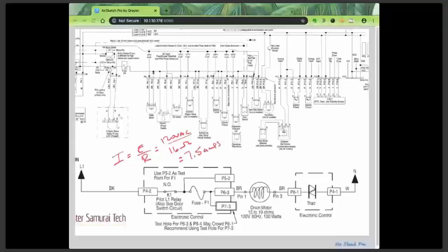A drain pump is going to sit there and draw 7.5 amps while it's running? That's like the startup current on a compressor. Is that reasonable? A drain pump drawing 7.5 amps, a little dinky drain pump motor. No, it's not reasonable. What went wrong? What did I do wrong here?